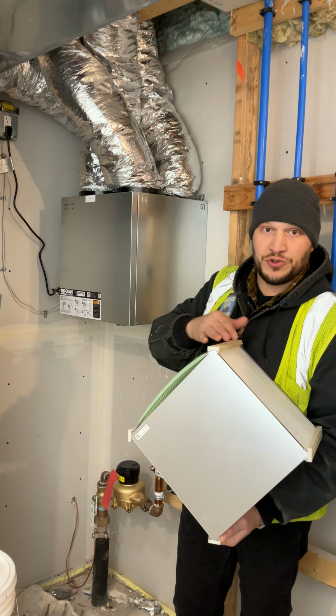So with your HVAC system up and running, it's important to measure your flows. You can measure your supplies and your returns. Here we're measuring a supply with a pressure flow matching device, and you can also use something like a flow hood, making sure that your flows are meeting your design values.